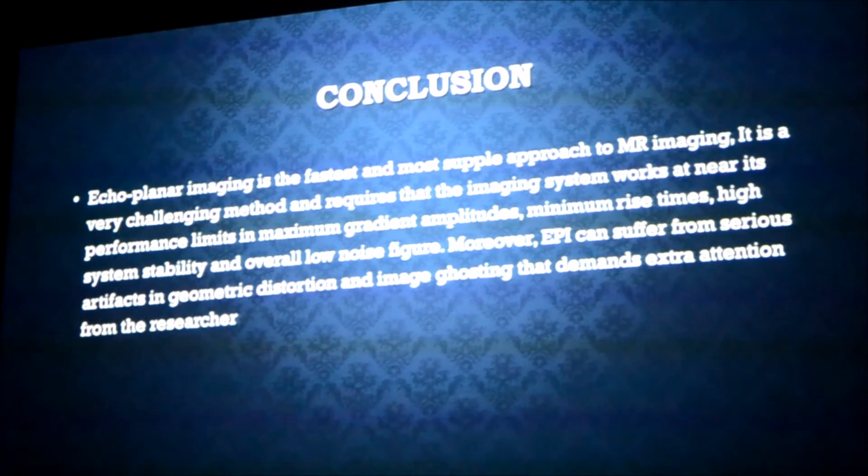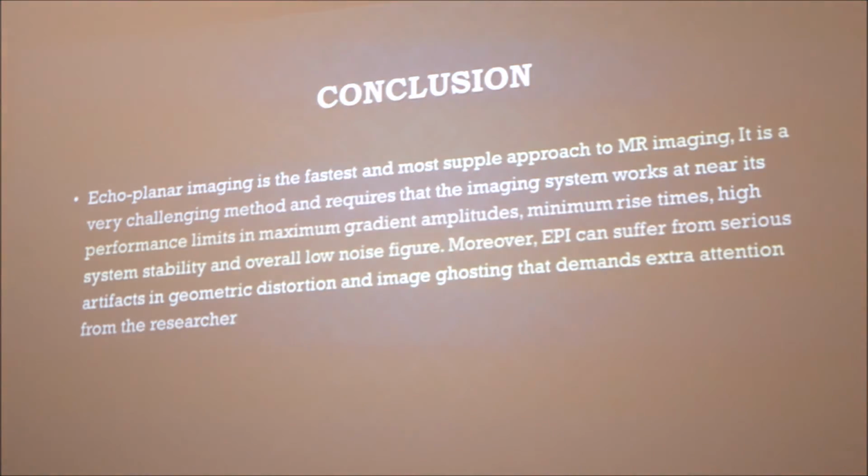So, in the end, echo planar imaging is a fast and simple approach for imaging. It's a very challenging method because the hardware demands are very critical, and our system is working at its limit due to very short rise time and very high gradient currents. Moreover, this imaging technique is very prone to different artifacts, and we can see Nyquist ghost artifact and chemical shift artifact in the normal EPI pulse sequence.